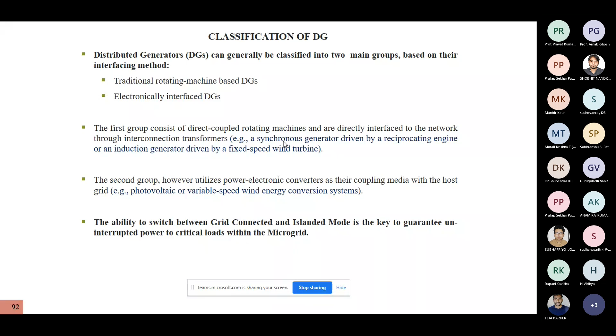These are all possible phenomena with respect to renewable penetration in the grid. But when it is a converter based DG that is penetrated, it is not only these factors that are taken into consideration, but also the associated control and its transition modes. For instance, we are taking a total operating time of the relay and the coordination time interval, CTI.